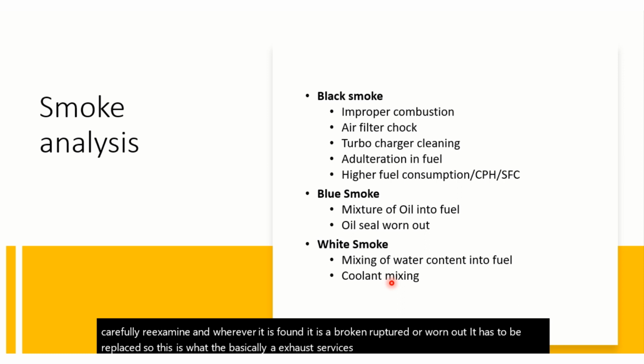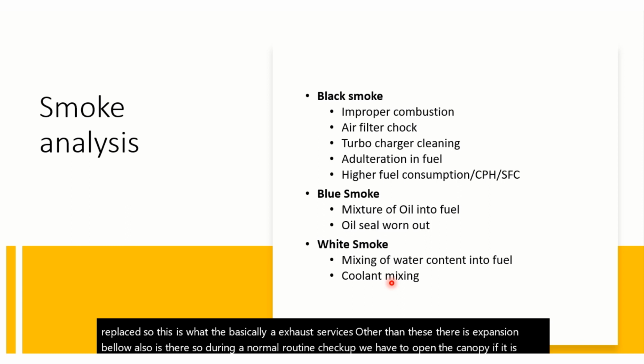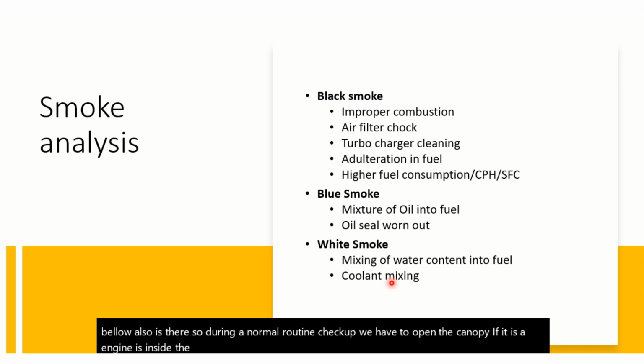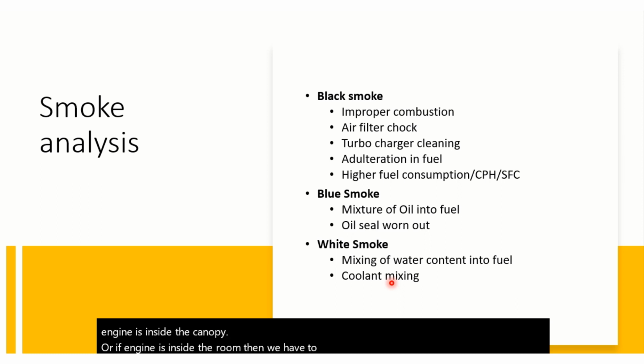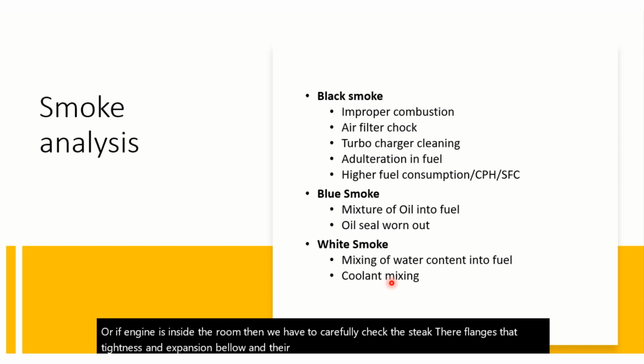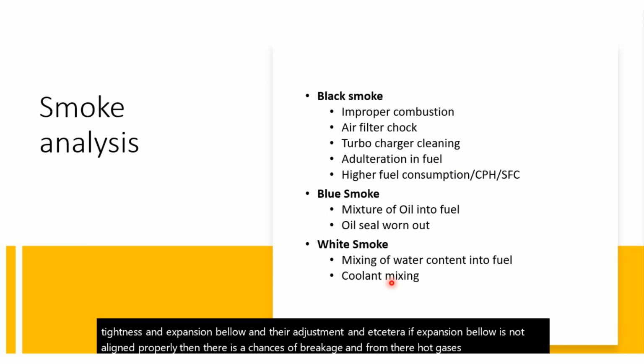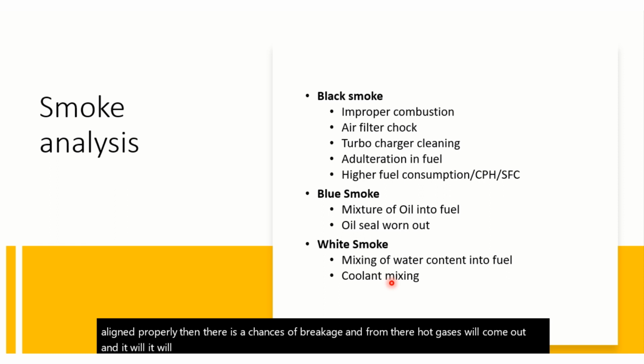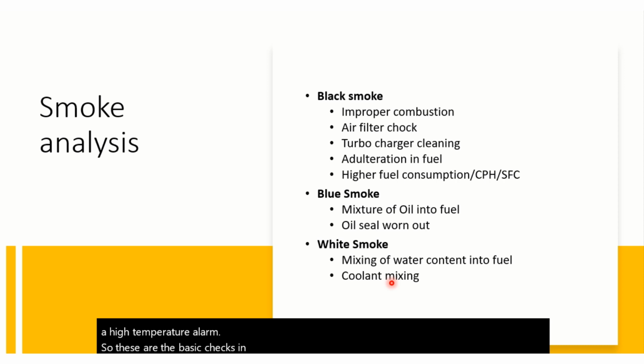Other than these, there is an expansion bellow also. During a normal routine checkup, we have to open the canopy if the engine is inside the canopy, or if the engine is inside the room, then we have to carefully check the stack, their flanges, their tightness, and the expansion bellow and its adjustment, etc. If the expansion bellow is not aligned properly, there is a chance of breakage, and hot gases will come out and completely fill the room or the canopy, which will further create a high temperature alarm. So these are the basic checks in the exhaust system preventive maintenance.